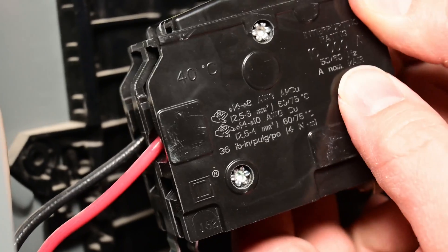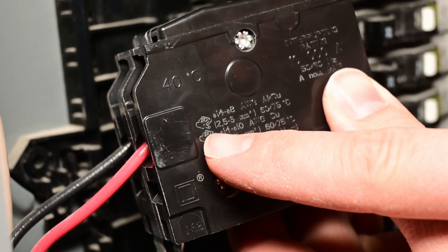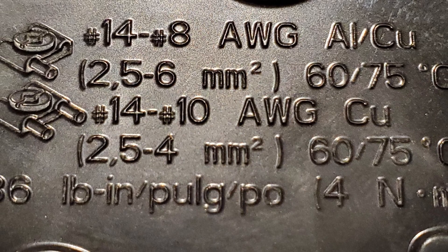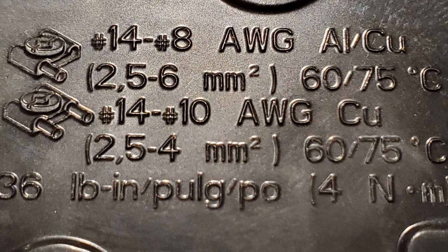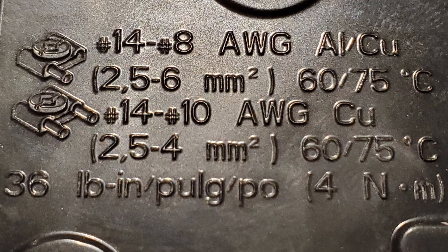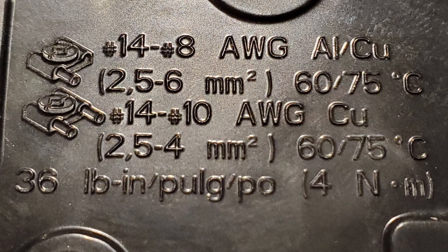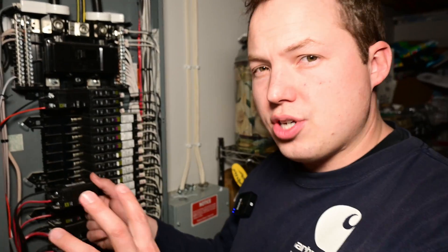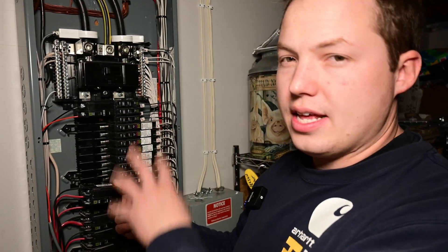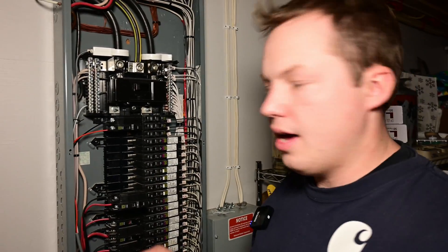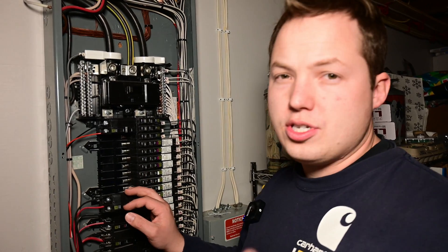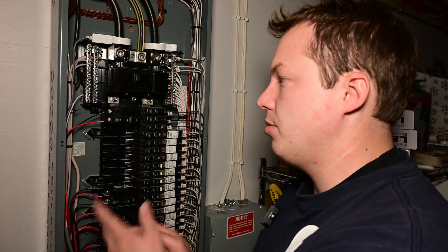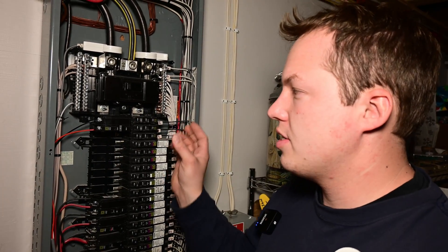If you look here on the side of this breaker, there is some detailed writing. This top diagram is showing that there's just one wire underneath the screw, and it says 14 to 8 gauge aluminum or copper. The one right underneath it says that it can have two wires of 14 to 10 gauge copper. So this actually can allow a second wire to be connected on it. So if your panel is totally full, I wouldn't be concerned at all about connecting the sense energy monitor to that breaker and piggybacking on the existing 240-volt circuit. Always check your local codes and talk to your local inspector to make sure that that's something that will be approved in your area. But if at all possible, install a separate breaker for the sense energy monitor and get the smallest available breaker for a 240-volt circuit, which most of the time is going to be 15 amps.